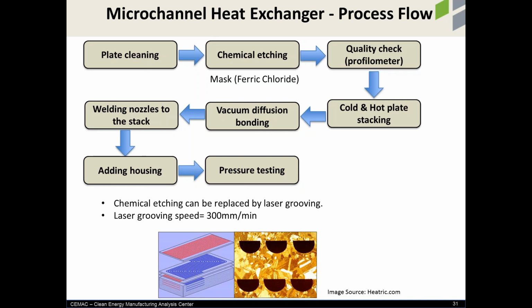Here is the manufacturing process flow diagram for making these heat exchangers. Starting with stainless steel 316 plates, we do cleaning, then chemical etching or laser grooving, followed by a quality check before stacking cold and hot plates on each other. The whole stack then goes inside a furnace under high temperature and pressure to allow diffusion bonding between the layers. After that we add other parts like nozzles and sensors, and do pressure testing for the whole system after adding the housing.